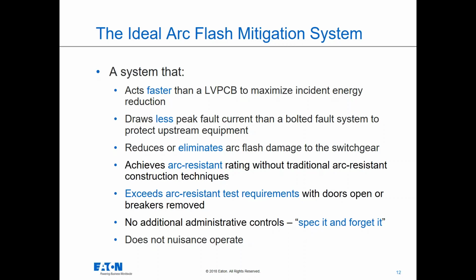My background with Eaton was about a decade's worth of actual field service. So I used to be one of those folks that had to go into systems that were most times dead, but sometimes you had to work on live systems and do some sort of maintenance or some sort of operation that required working around live equipment. And I can say that most customers, when I would visit them, wouldn't necessarily be aware of all the things they needed to do to safe out their equipment properly, because it's not an activity that they do on a regular basis. So something that's passive and always operating in the background to protect would be ideal.